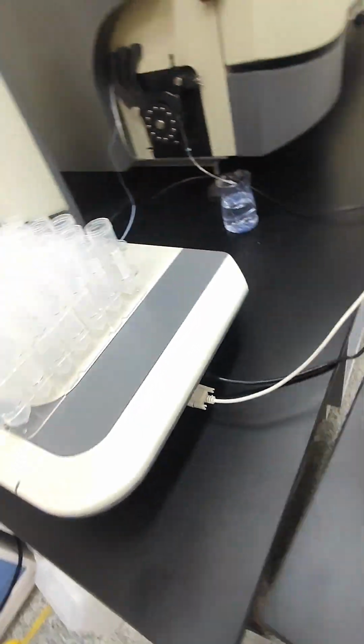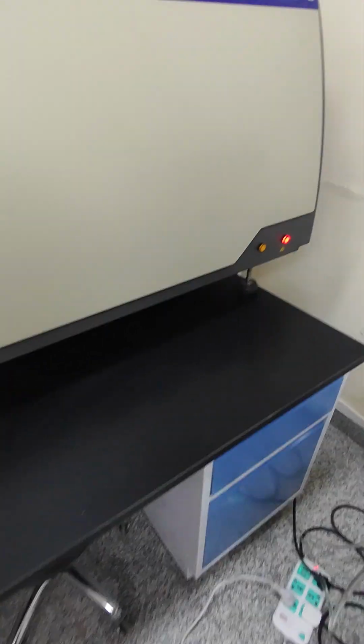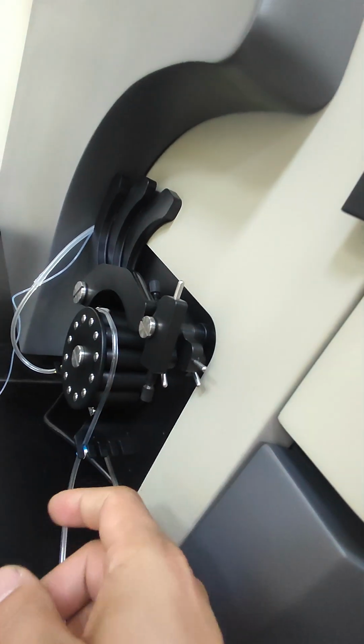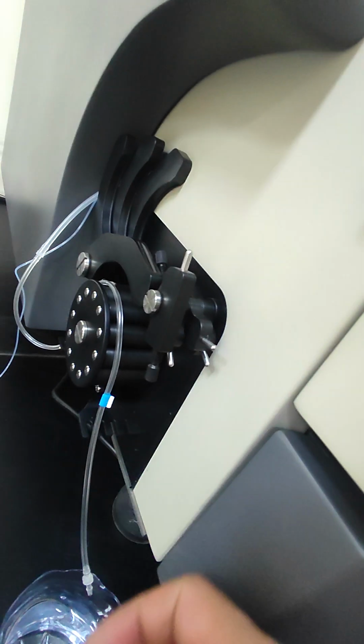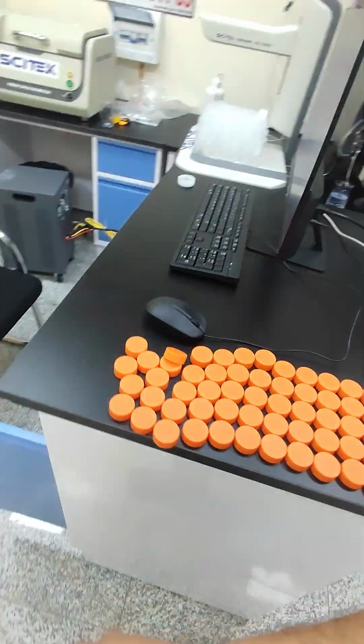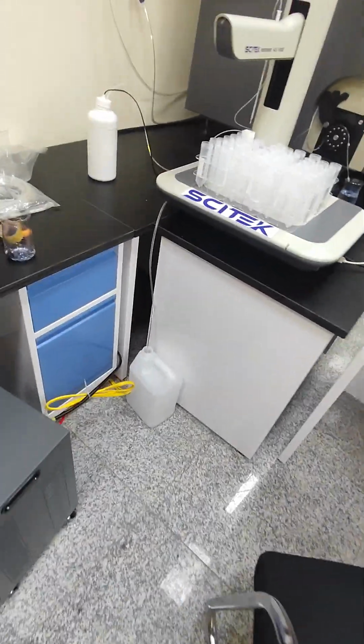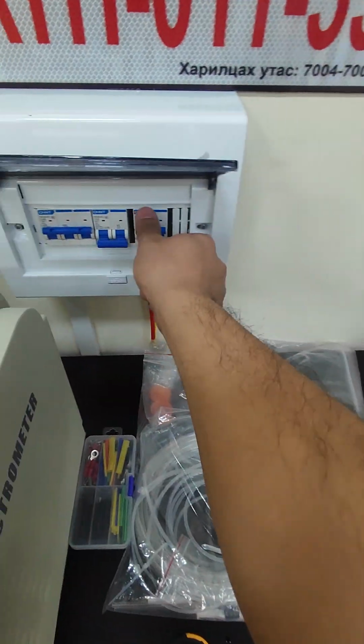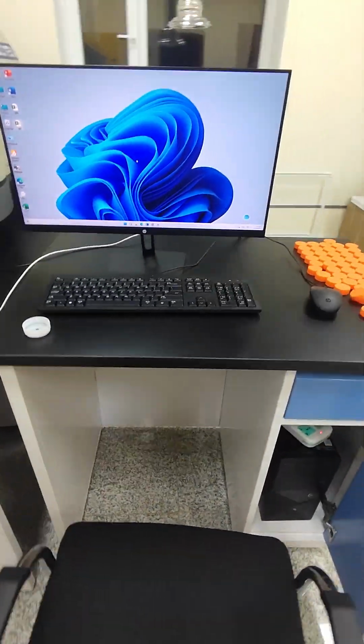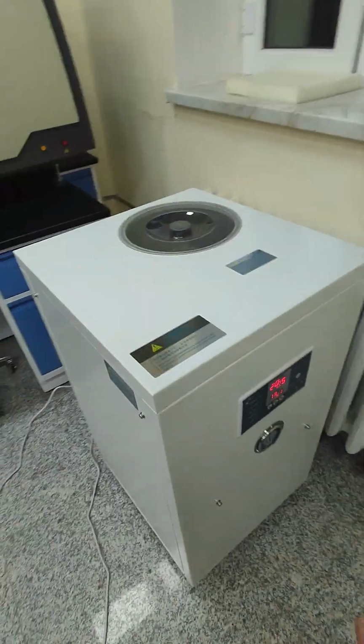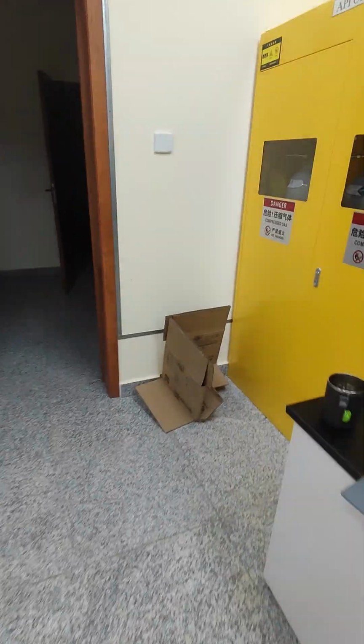And the auto sampler can be turned off. The machine can be powered off. Also the black one first, then the red one. And we need to release this pump tube. If it's not released for a long time, it will not work well. We need to release it if we're not using it. And then we can power off the UPS and the main power supply. For the water chiller, I suggest turning it off after 10 minutes. For the blower, you can keep it on or off, it doesn't matter.